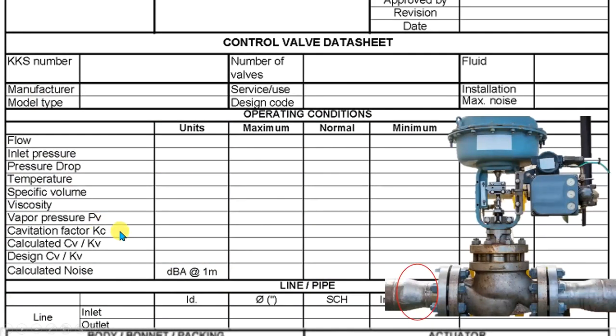Cavitation factor here is only applicable to control valves and indicates the possibility of cavitation in the valves. I will put a link for whoever wants to know more about cavitation. Then we get to the most important parameters in this section, which are CV and Kv. Generally, CV is the valve capacity at any of the three operation points to handle the corresponding flow rate, and will be the main parameter in valve sizing.